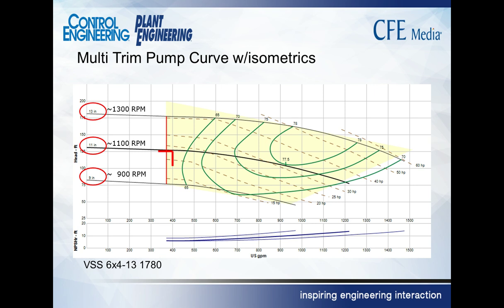How does atmospheric pressure affect pump performance? For example, sea level versus 6,000 feet. It has very little effect on anything that we've talked about, because in everything we've talked about in this presentation, both suction and discharge are subject to the same atmospheric pressure. And the total dynamic head is discharge minus suction, so if you put it on both sides, it makes no difference.